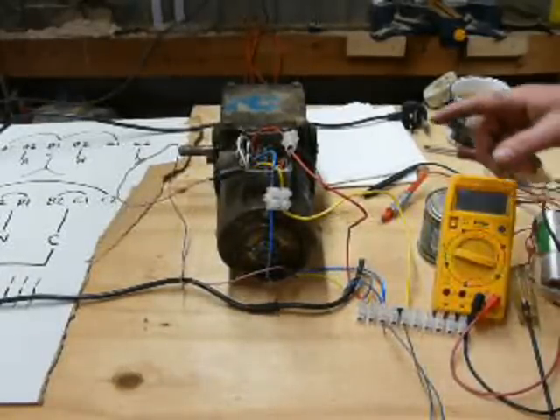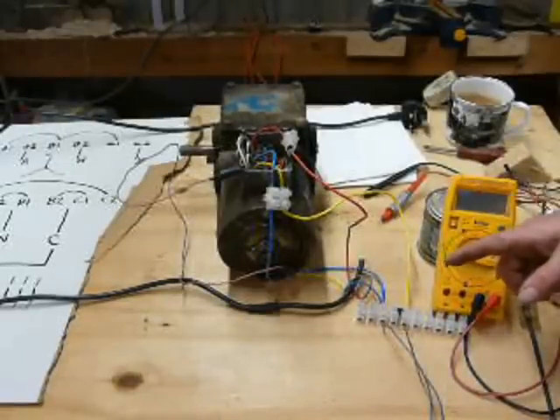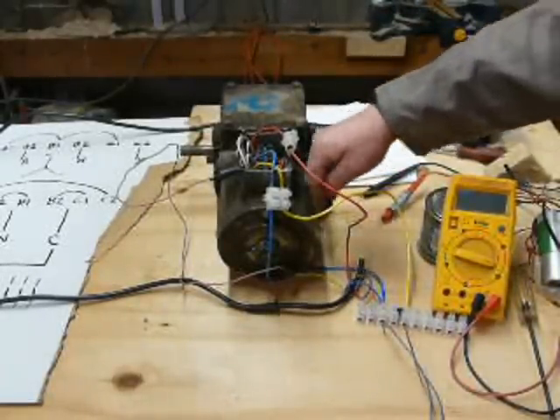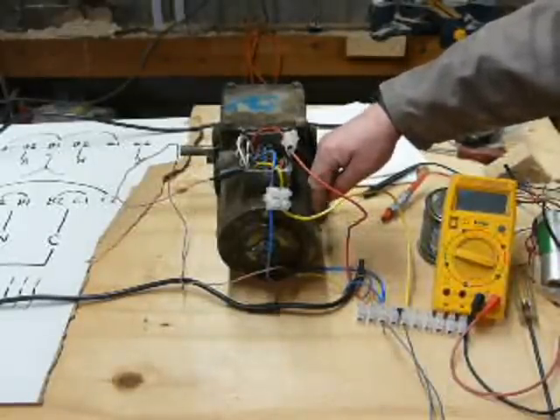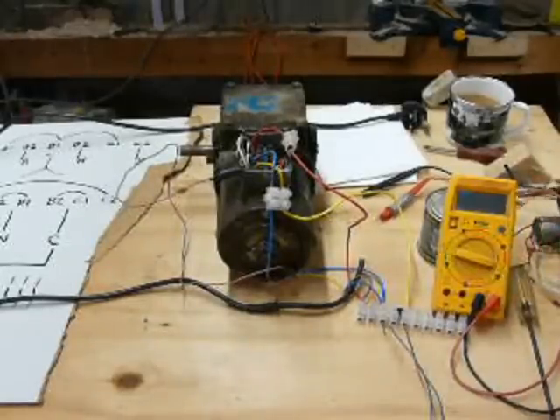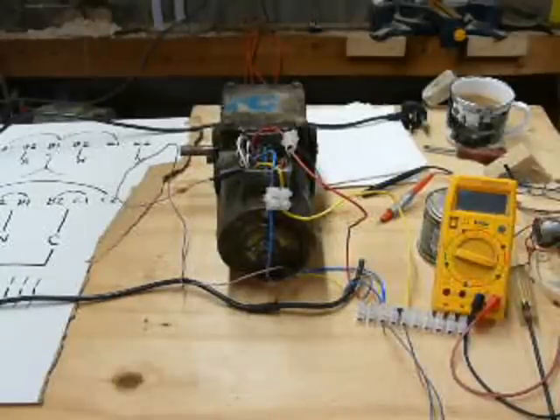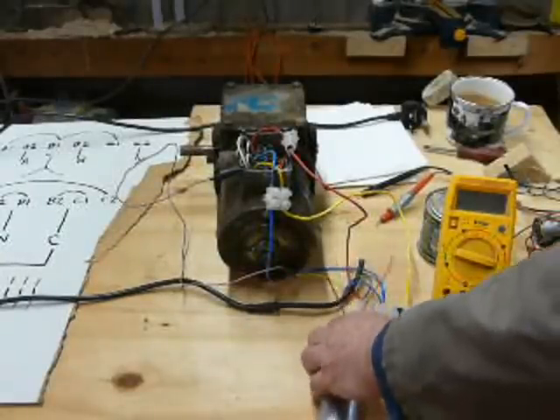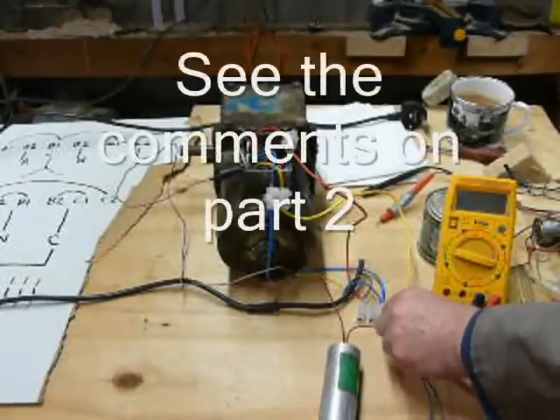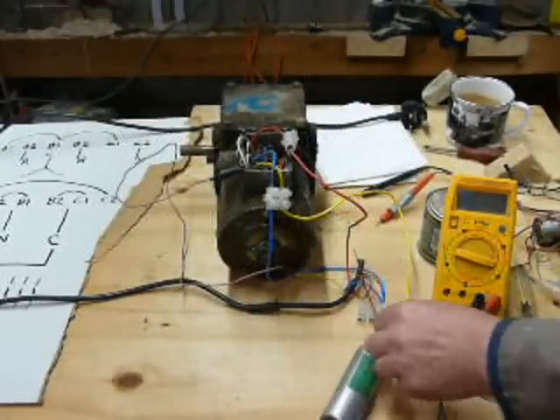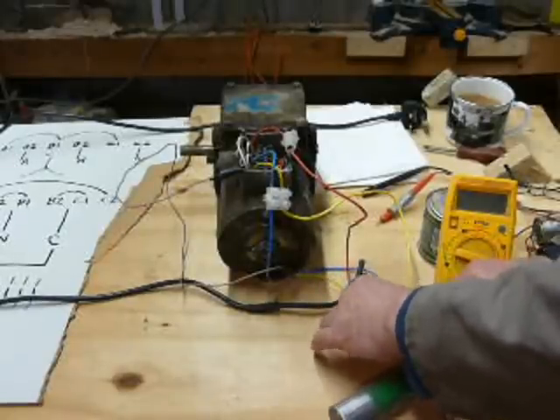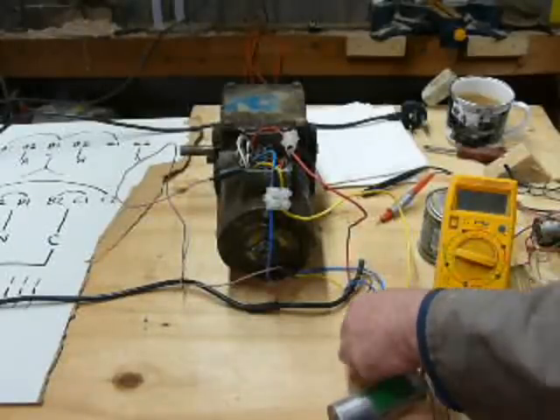Right, so you can see that if you put too much capacitance on, then the volts go up. And of course, the coils in this motor, because we've changed it to 240 volt operation, when you start putting 260, 280, 300 volts in there, of course the coils will get warm. So that was interesting. And I can't remember the guy's name who emailed me about that, but he's got a video on there showing start capacitors and measuring the voltage. Thank you very much for that, it's much appreciated. You know, it was just the idea, well, measure it. It's not rocket science, but you've got to think about it.